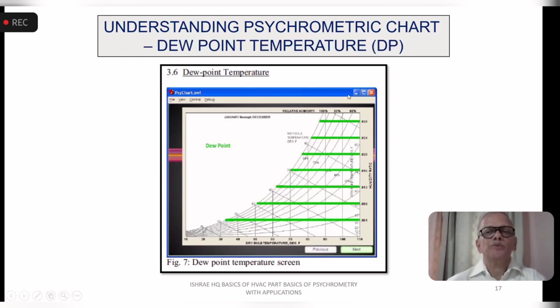Dew point temperature is one of the important parameters to understand. This dew point temperature is the temperature at the saturation curve, which means it is 100% saturation, and it is a function of the moisture content. So if that is the value of the moisture content, you draw this line horizontally and meet the saturation line, which means it is 100% saturated. So for this moisture level in the air as a sample, the dew point will be here. As the moisture level is higher, you see here, this is higher than this, so the dew point is higher. So as you have more moisture in the air, the dew point of that air will be higher. What it means is, the condensation will start occurring at a higher temperature.